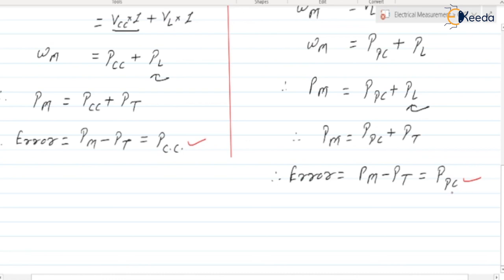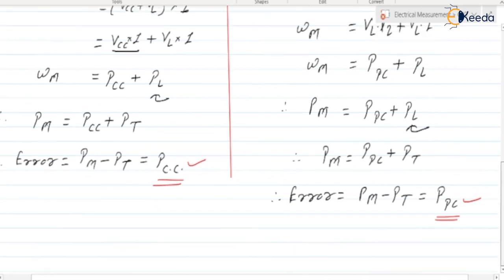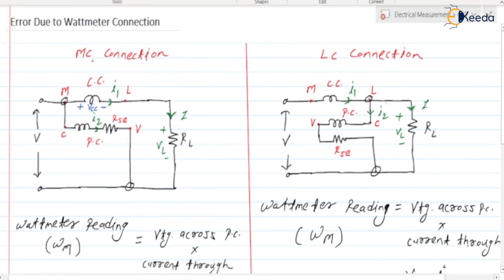In summary: in the LC connection the error is due to the power consumed by the potential coil; in the MC connection the error is due to the power consumed by the current coil. These questions have been asked in previous GATE examinations. In both cases, the error is due to the coil connected on the load side — in MC connection the current coil is on the load side, and in LC connection the potential coil is on the load side. This covers the error due to wattmeter connection type. Thank you.